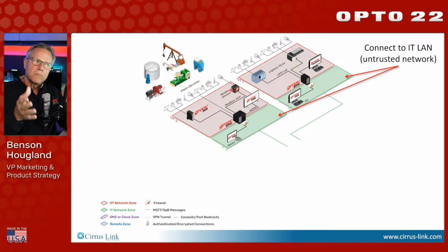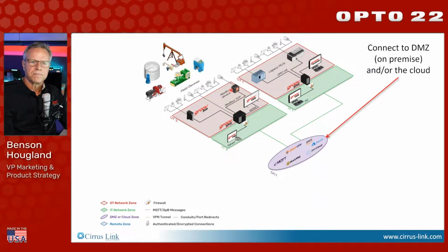So now the next step, and this is an important one. These edge devices have multiple network interfaces. So I can now use that to connect to an IT LAN or some other LAN that may be untrusted. Why? Because the edge device on that given port has the kind of security capabilities that you would normally find up in IT. I'm talking about firewalls, certificates, user authentication, multiple network interfaces, and valid gateways to other networks, right on the edge device. So here we're basically zoning out the 2: the trusted network, the OT zone, and the untrusted network, the IT LAN.